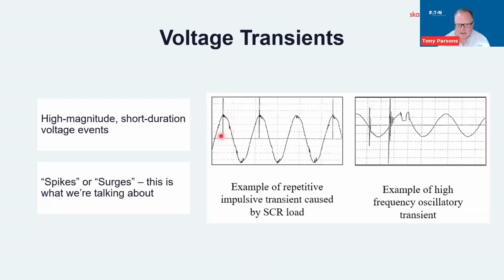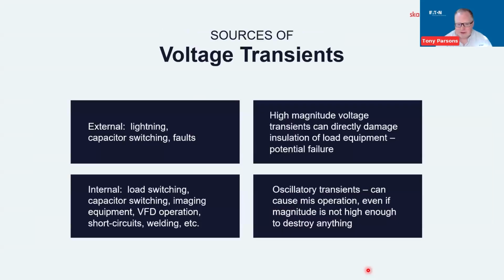On the graphs on the right-hand side, you can see the voltage sine wave, but you see the very brief, very high magnitude excursions from that. Those are the transients. On the left-hand side, we've got impulsive transients. They hit and then they go away. On the right-hand side is one that may be more characteristic of switching a capacitor bank online. We have some oscillation. We call that an oscillatory transient, and it can result in extra zero crossings of the voltage, where we go across the zero axis. Sometimes control equipment uses those zero crossings as a reference, so you can actually foul up the controls in some ways. If someone talks about spikes or surges on the network, this is what they are talking about.